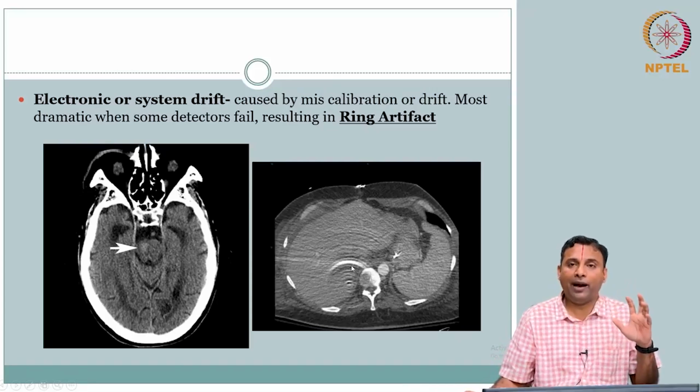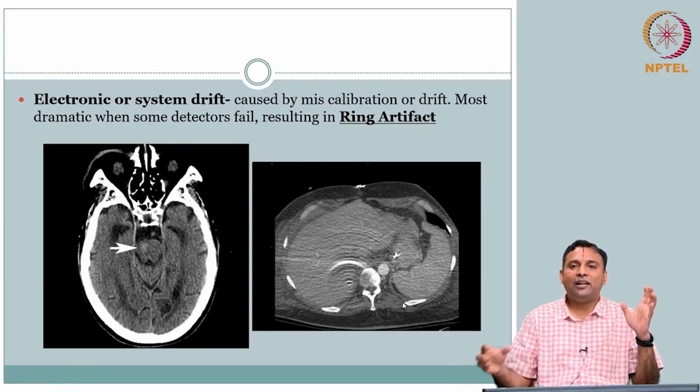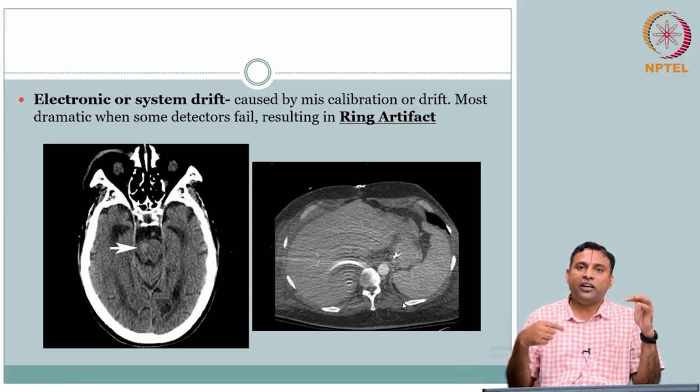I mean, it's not really a pattern that is there inside. But at least one ring, if it is there, is it a circular lesion or some circular growth, or is it because of malfunction? Again, domain expertise and experience come into the picture, but if you get nice circular symmetric patterns, in all likelihood it is because of your reconstruction algorithm.